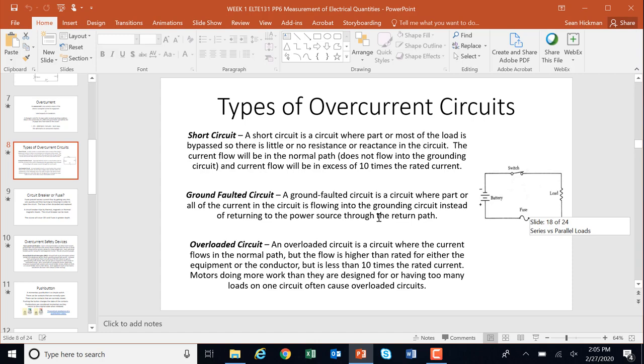A ground faulted circuit is where part or all of the current is flowing into the grounding circuit. What that means is that if you have one amp leave your source, you really want one amp to come back into your source. If the ground is taking some of the current away — let's say you had one amp leave and only a half an amp return — well, then you lost a half an amp, and that half an amp could be going through you, which would be dangerous. So we have GFCIs, which you see in your house in your bathrooms, kitchens, and garage. What they do is they say: I've sent out one amp and I didn't get one amp back — and so they trip very quickly.